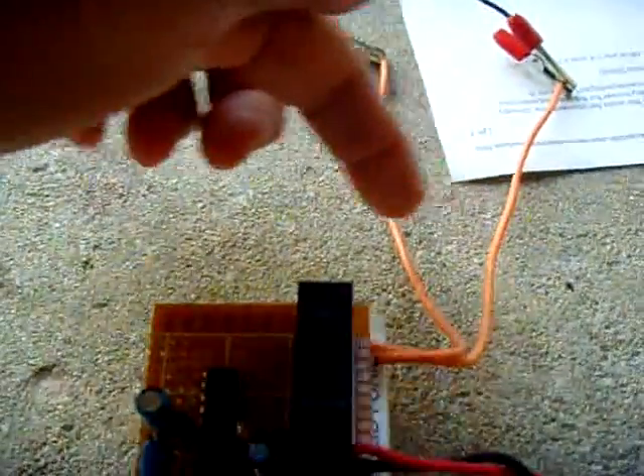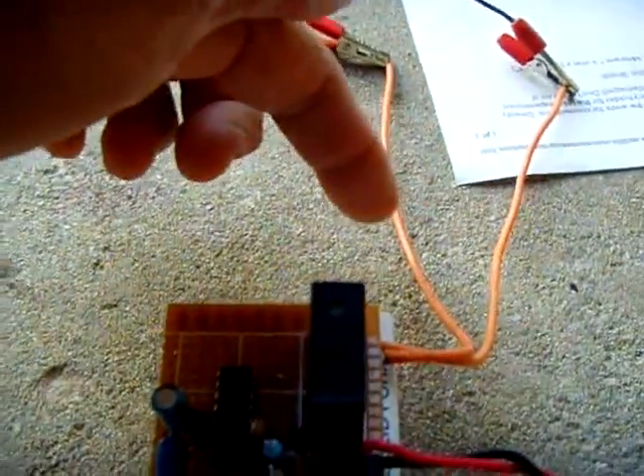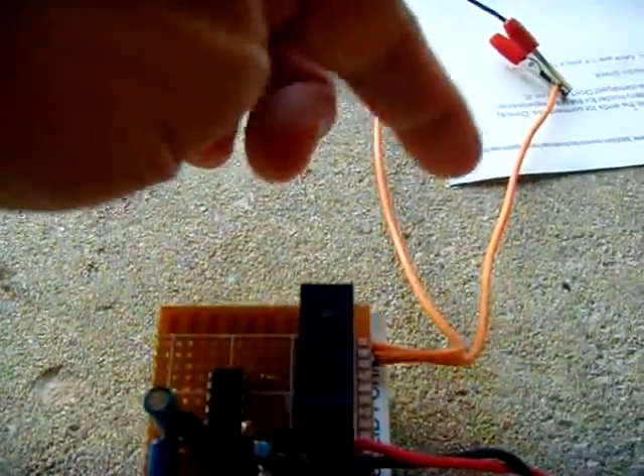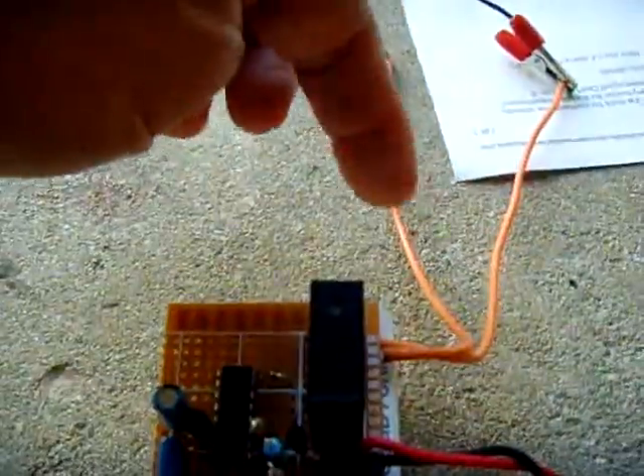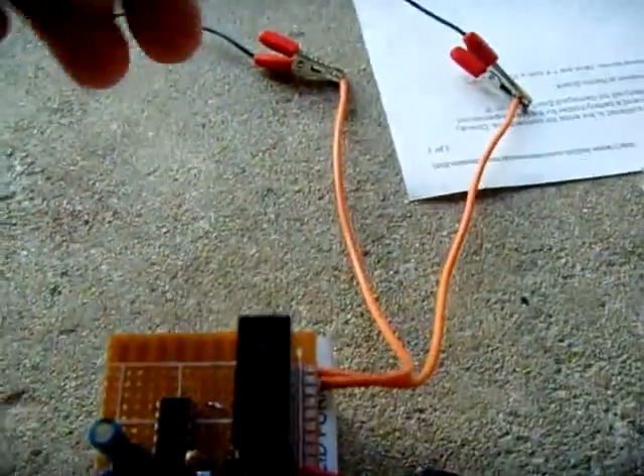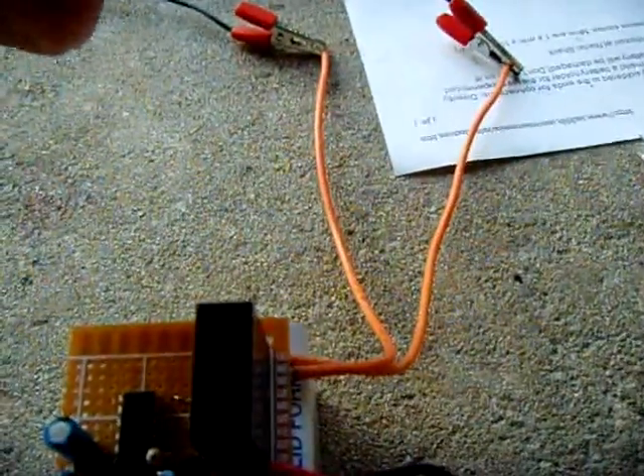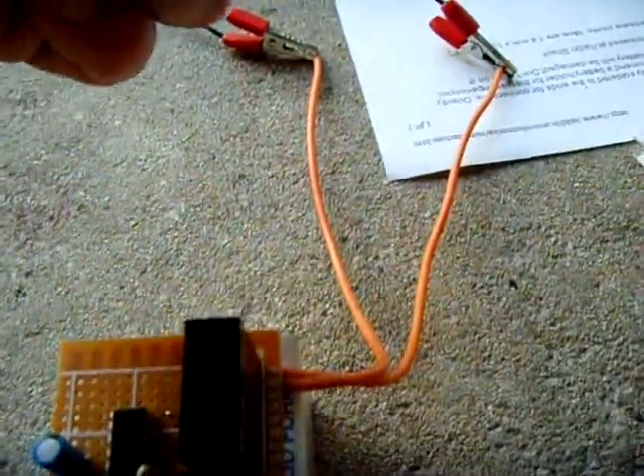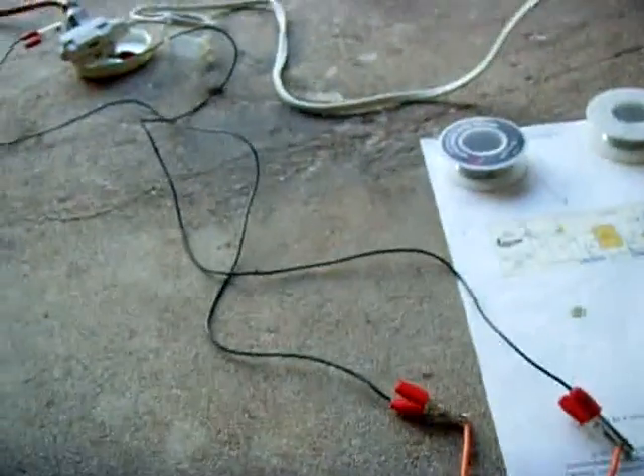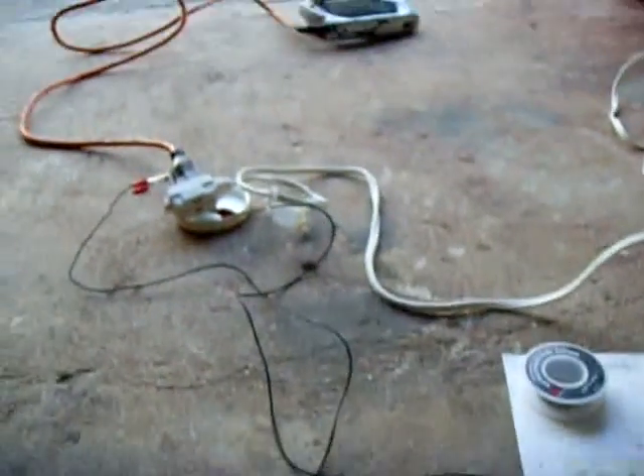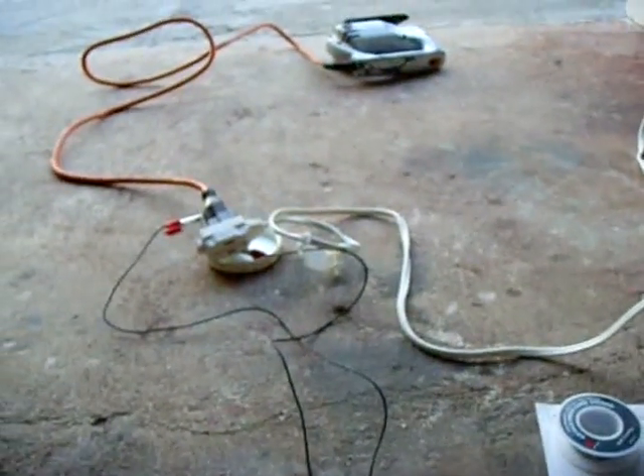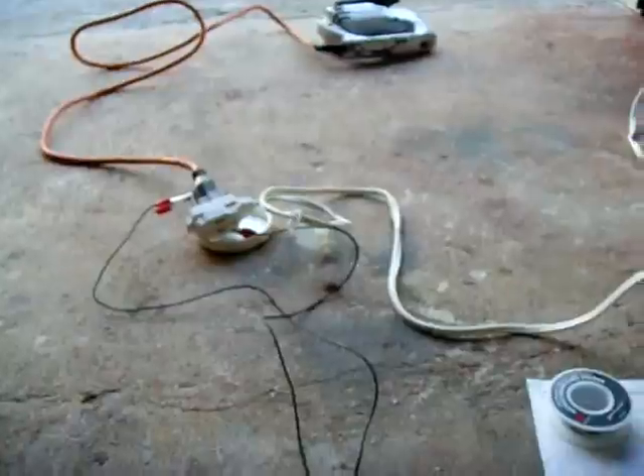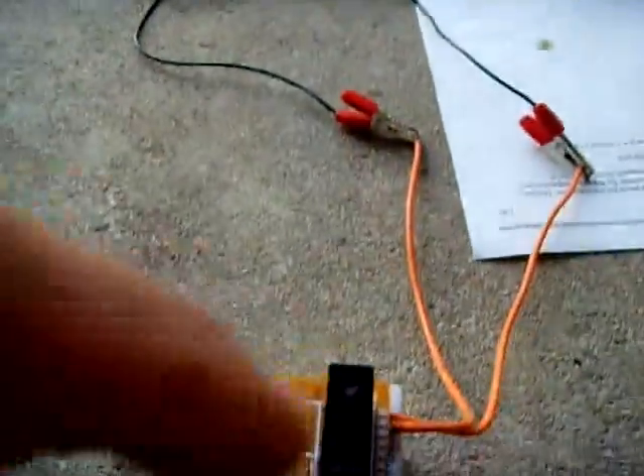These two wires go to the other side of the relay, so when the contacts close, this becomes one loop. You want to make sure the hot, not the neutral, the hot goes through the relay. Otherwise, you're going to leave the appliance always hot. You don't want to do that. So make sure the hot goes into here.